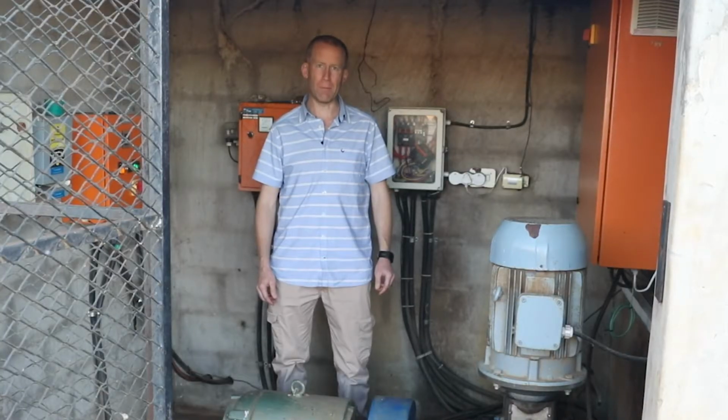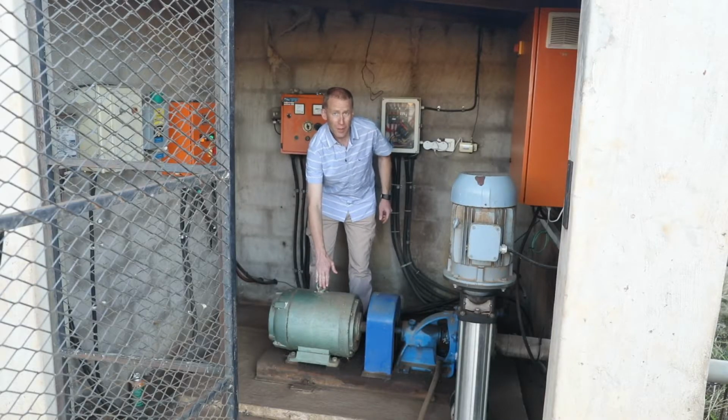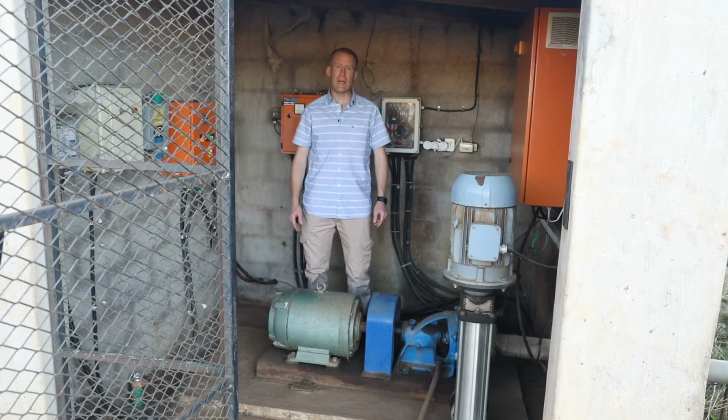I'm standing at the pump house for Pivot 2 on My Hill Farm. This is the original pump and motor for the Pivot. It is a 30 kilowatt motor, and when it was running the Pivot, the motor was drawing 22 kilowatts. We tested the complete system and found that the pump and motor were completely oversized for the flow rate required by the Pivot. This is quite typical of many systems that we test.